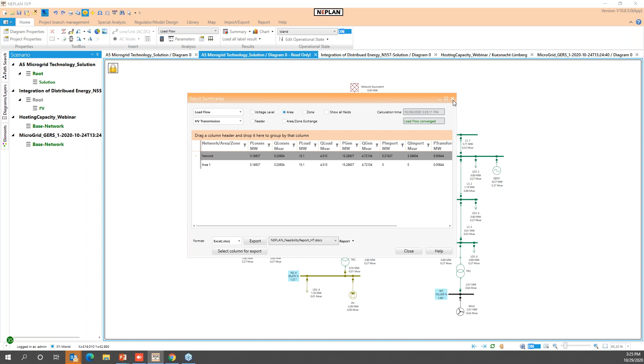Finally, two main points before we come into what we call hosting capacity. We have here another microgrid. In this case, if we run the system, we can see that the voltage is, as the drawing shows, exactly 114. So we are exceeding the voltage. Why does this happen? Because we are generating only 100 kilowatts, but the distance here is extremely long. It's 49,000 feet, which is more or less equivalent to 15 kilometers.